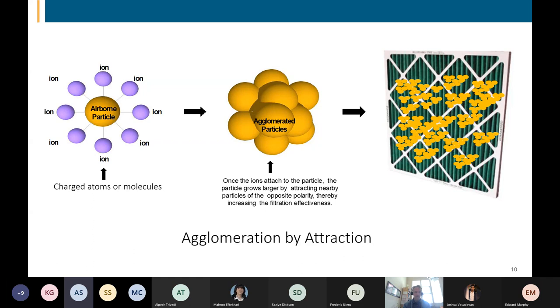So for example, you may buy vendor A's ionization technology and install it in the HVAC system, and then you might purchase and install vendor B's air measurement and verification system. It could do temperature, relative humidity, it could do CO2, it could do ozone, it could do formaldehyde, it could do ions, it could do particles, PM10, 2.5 and smaller, it could do VOCs and things of that nature, if you want to prove efficacy. And I highly recommend that on anything that you install.